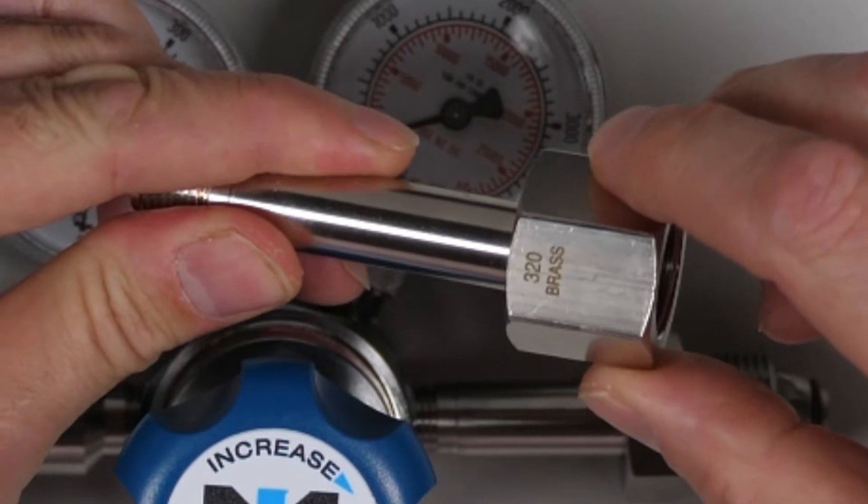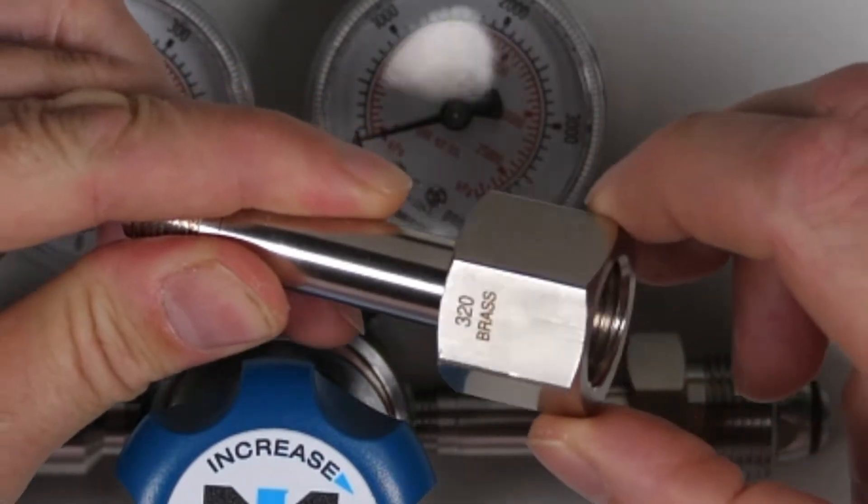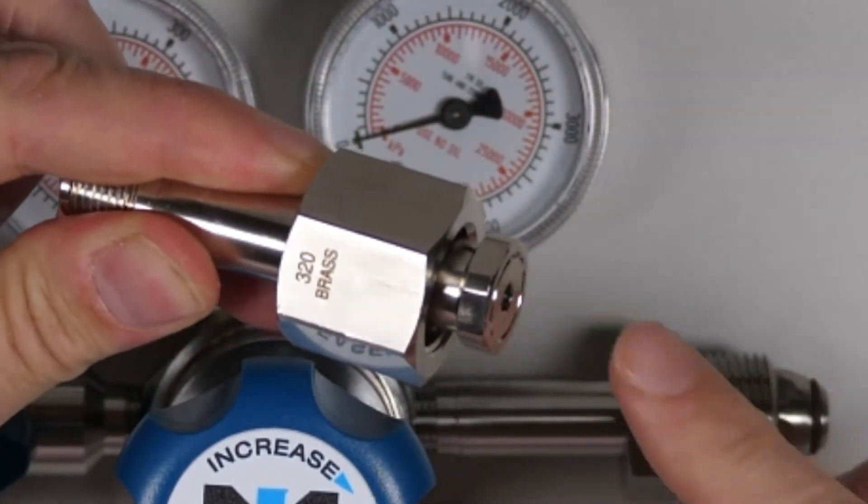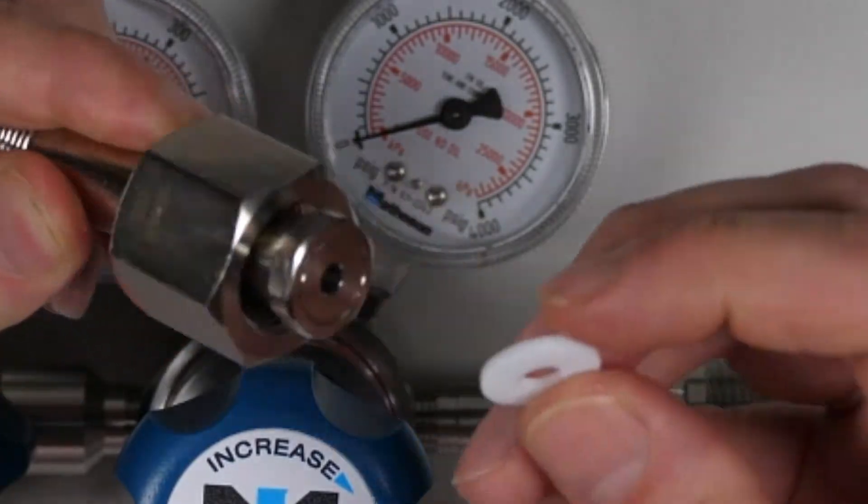The CGA 320 fitting for carbon dioxide cylinders has a flat-faced nipple and needs a washer.